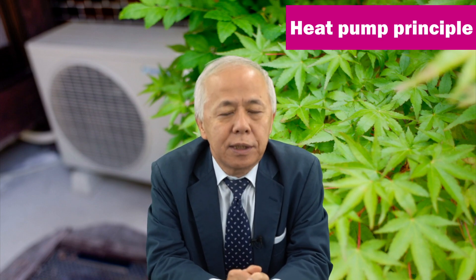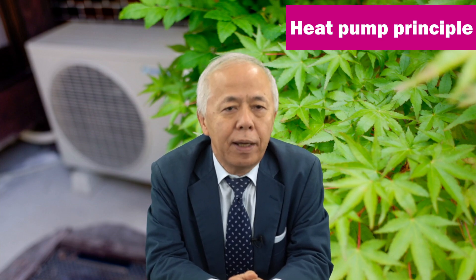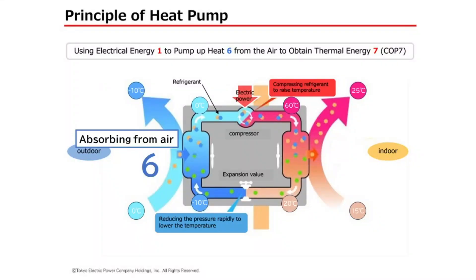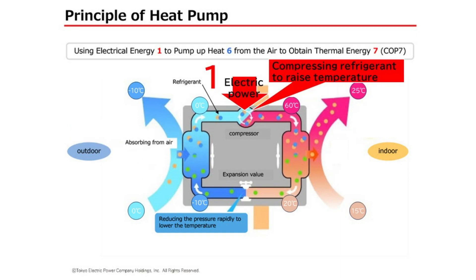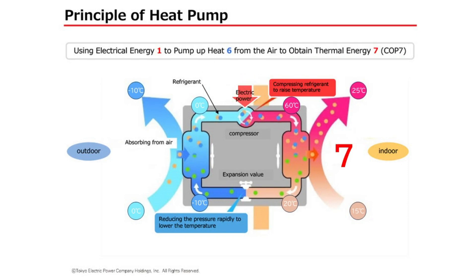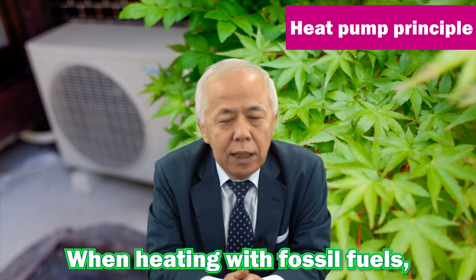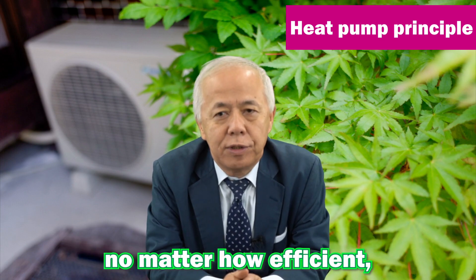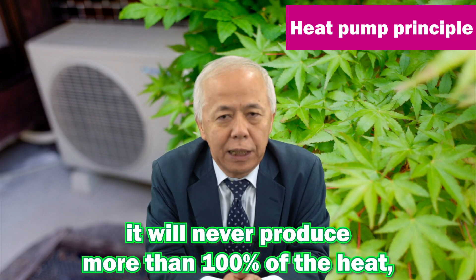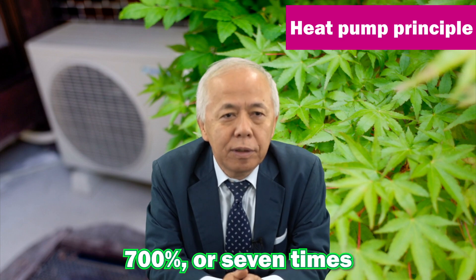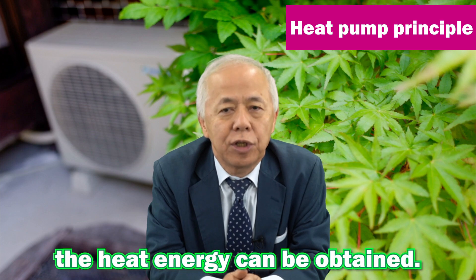The only part of this process that uses electric power is the part that operates the compressor. In this illustration, by pumping six units of heat from the atmosphere, one unit of electrical energy is used to deliver seven units of heat energy to the room. The performance of a heat pump is expressed in terms of COP, coefficient of performance, and the heat pump in this illustration has a COP of seven. When heating with fossil fuels, no matter how efficient, it will never produce more than 100% of the heat. But with the heat pump, 700% — or seven times the heat energy — can be obtained.